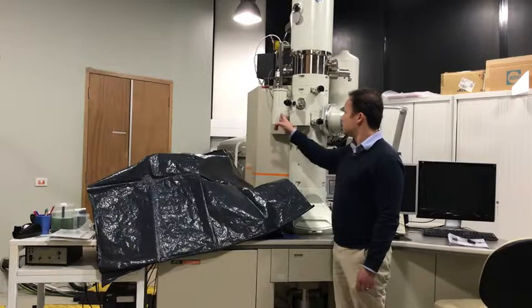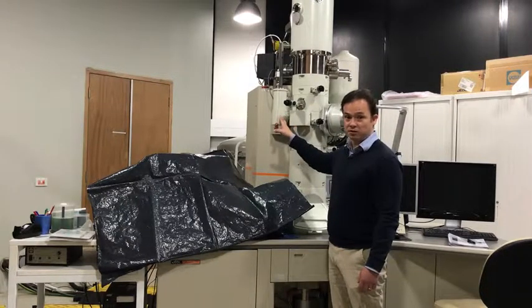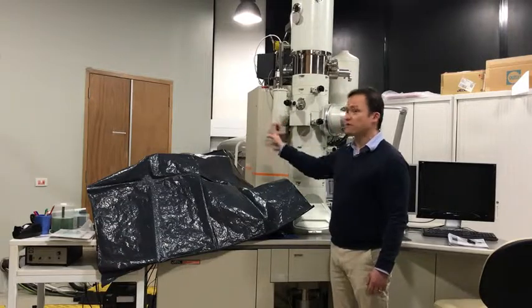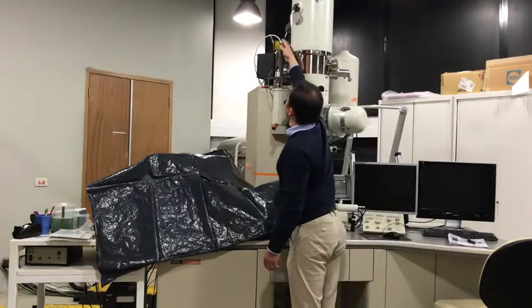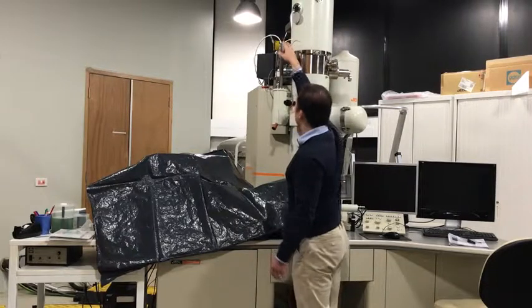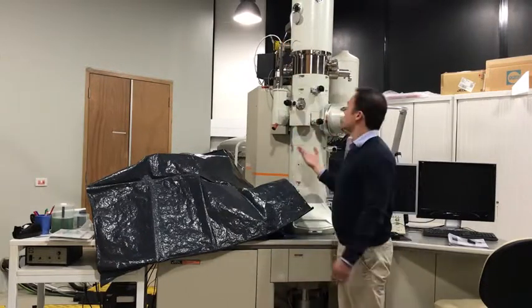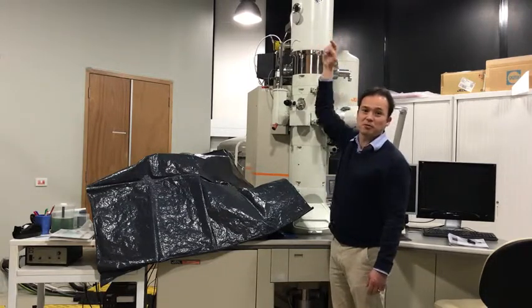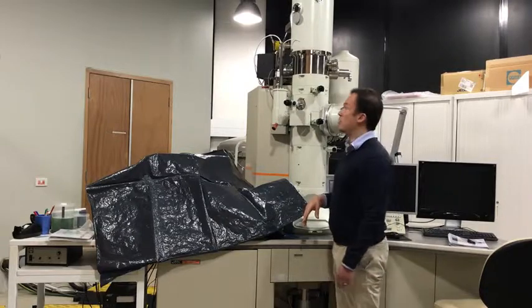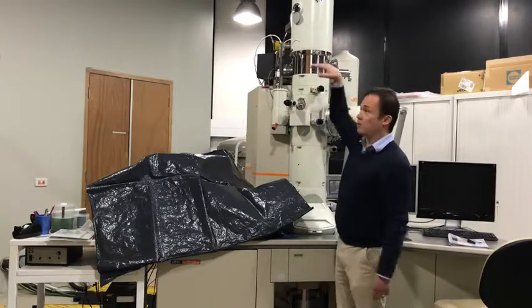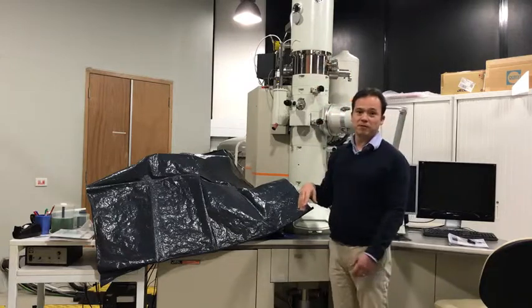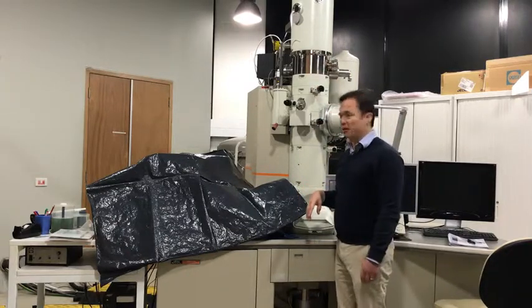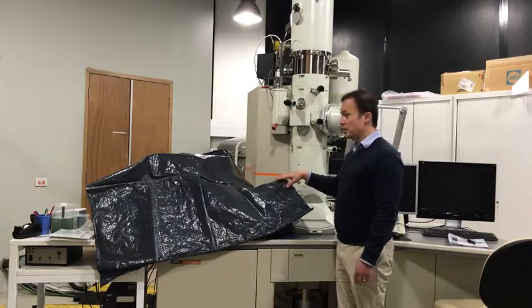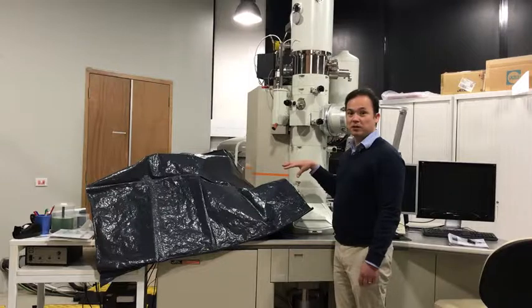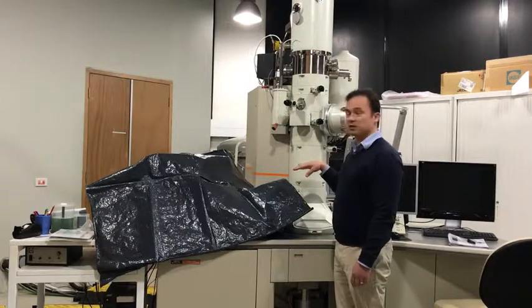They had to heat up the cold finger and drive off all the liquid nitrogen, and that means the liquid nitrogen can fly everywhere, because it comes out of a little hose up here, and I'm a good scale bar to show you how tall this is. You can't see the top of the column because I couldn't move the camera tripod far enough back or zoom out far enough to see the very top of the column, but the bit that's cut off, there's probably another foot of gun above the frame of the video. So this sheet is here because I'm about to go and get some liquid nitrogen and start the crucial part of the process of starting up the instrument.